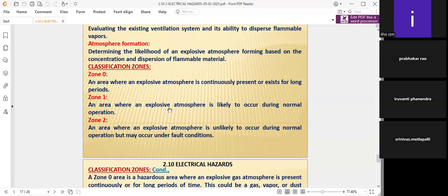Zone 1 areas: an area where an explosive atmosphere is likely to occur during normal operation. In normal operation, where explosive materials or an explosive atmosphere are coming into the industry, either class 1, class 2, or class 3, we have to see that it is likely to occur in normal operating conditions as well. It does not occur continuously. An area where an explosive atmosphere is likely to occur during normal operation comes under zone 1, and we treat it according to the control measures as per the classification.